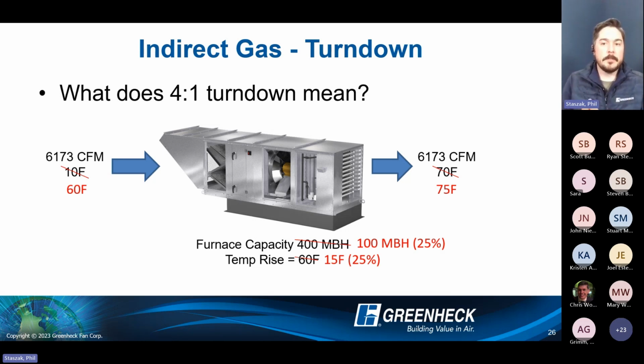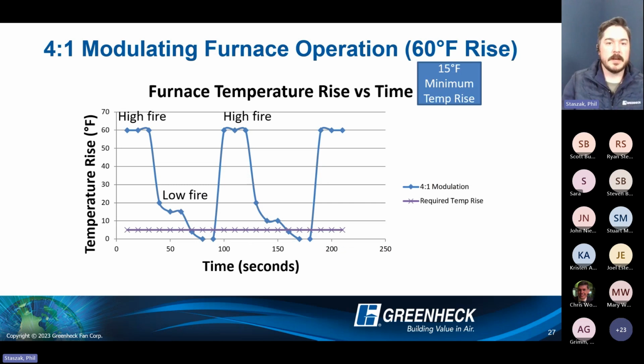So high turn down capacity is very crucial. The higher the turn down, 25-to-1 built into direct gas fired equipment, now up to 16-to-1 with indirect gas fired, but obviously there are more costs associated with that. So typical is 4-to-1, and that's the math and what that actually means. The higher the available turn down, the tighter the temperature control that you'll have no matter what the outside air temperature is. So what does that look like?